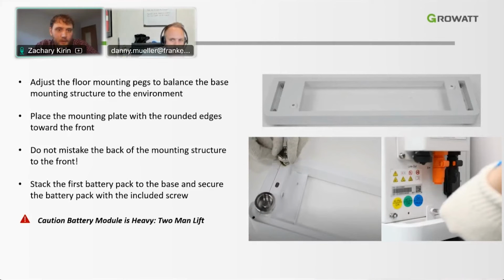Here's a little bit about the floor mounting plate. Again, it is adjustable, so if the floor is not quite even, you can make the adjustments needed to get a floor stand that is very reasonably level with the surface. We'll place the mounting plate with the rounded edges facing forward. I know this picture doesn't do a great job, and if you don't have the product in front of you it doesn't help, but there's a square end and there are the round ends. This is how I know exactly which end is supposed to be facing the front. We want to make sure that the battery modules are installed in the proper orientation. Once you have the floor plate ready to go, you will install the first battery pack to the base. It's just as simple as lifting the battery on, putting it down onto the base, and then screwing it so that it is secure. You'll screw it with the included screws, and then the added tab here to secure it to the floor base. And again, I do want to mention the battery can be a little heavy. It's a 2-man lift in certain applications.